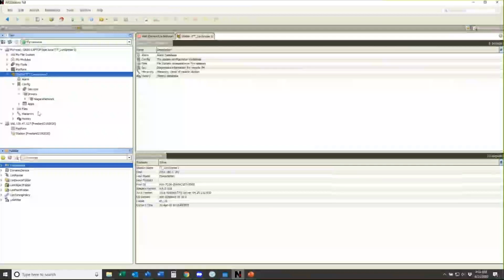You would probably be working from your laptop, but you could also bring a Jace out to the job and connect up to it. You need a network interface of some sort—by that I mean the expansion module that comes on a Jace, or the LON stick. You need some means of communicating between the N4 and the physical topography. That's called a network interface.